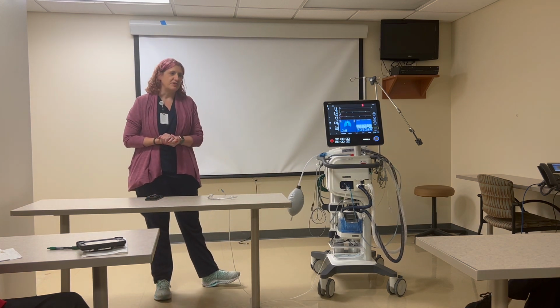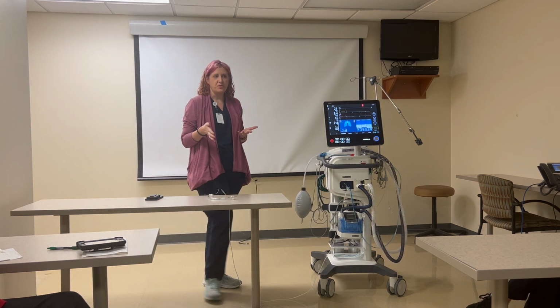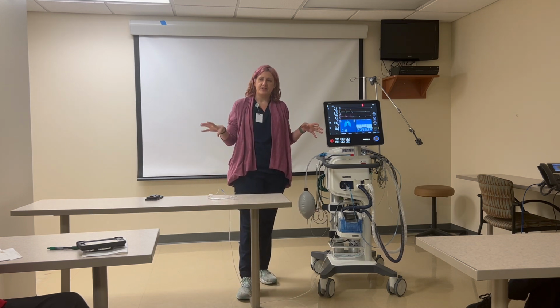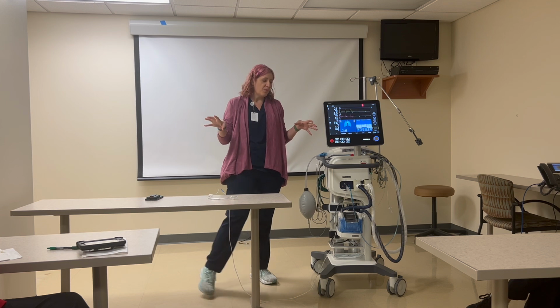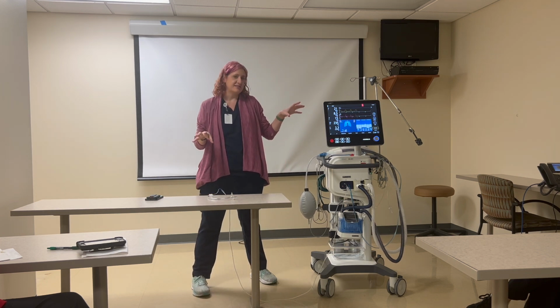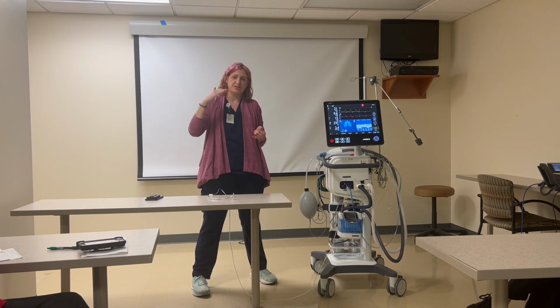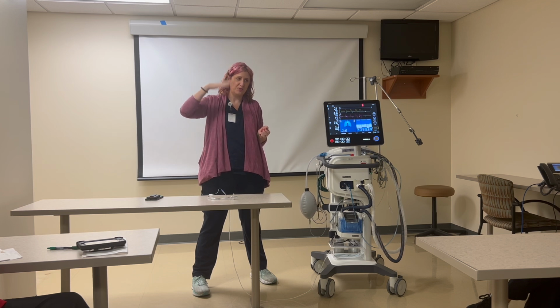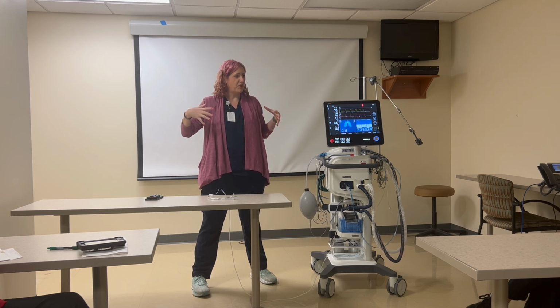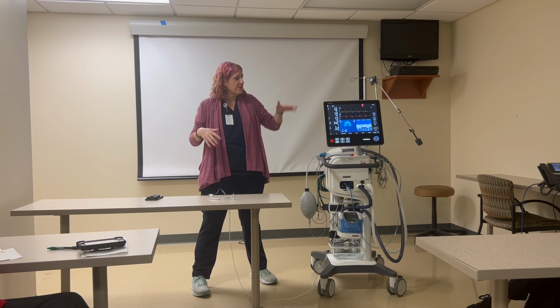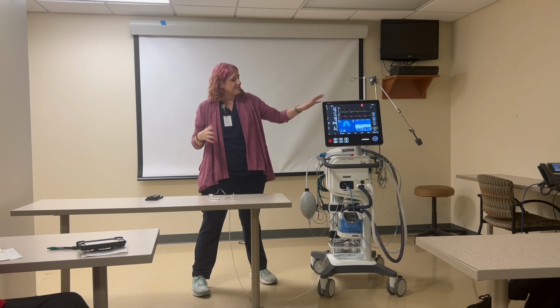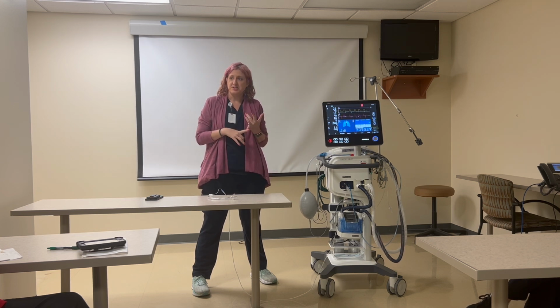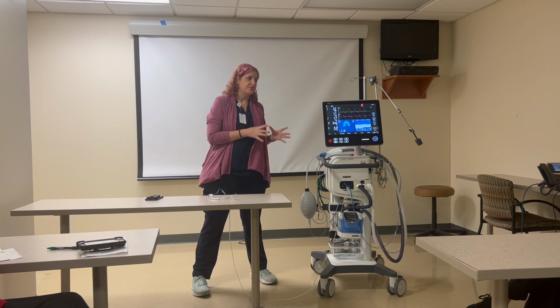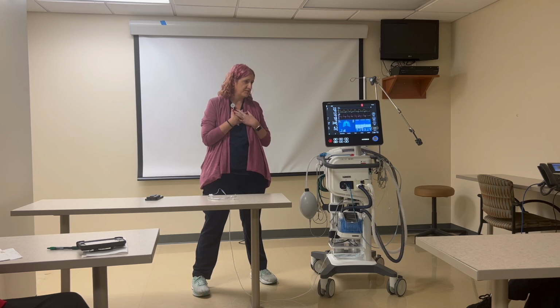and that is something called ASV, or adaptive support ventilation. ASV is a Hamilton specific mode. You will not find this on another ventilator. What it is, RT will set a minute ventilation. Minute ventilation is our respiratory rate and our tidal volume multiplied together to tell us how well our patient is working to breathe. So by setting a minute ventilation, that allows the ventilator then to choose the patient's respiratory rate, tidal volume, I time, and pressure, and adjust all those settings in the background, keeping the patient comfortable.